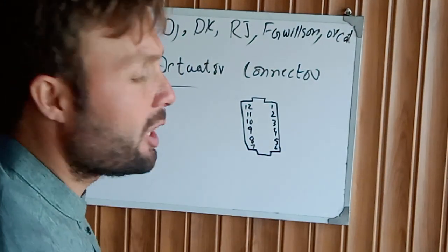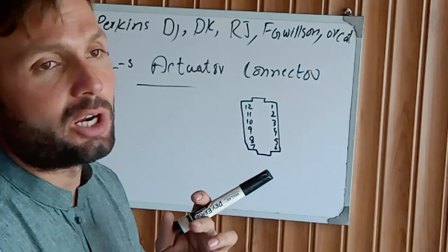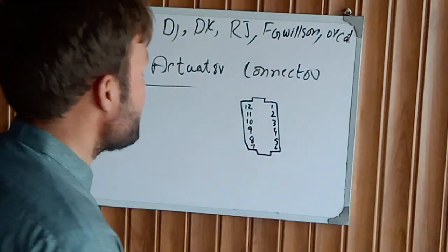Crack the fuel line and crank the engine. If diesel is not coming from the injector pipe or fuel pump pipe, that means the actuator is not working.